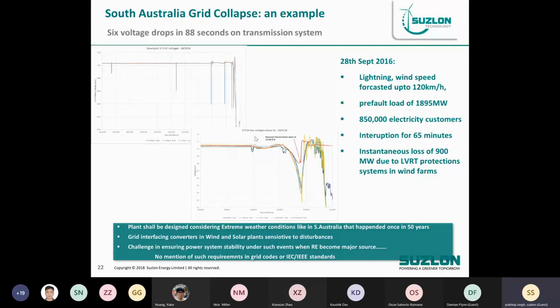Most of the wind farms, one after another, start tripping because of the LVRT events. On the top left side, there were 6 LVRT events of very small duration, something like 120 to 200 milliseconds, up to 50% to 30% dip. And 6 such events happened in less than 2 minutes time.